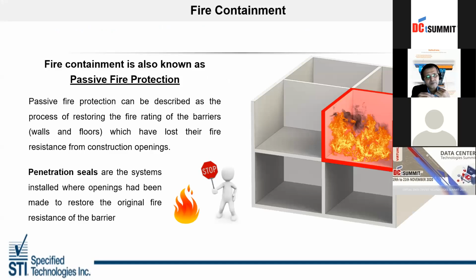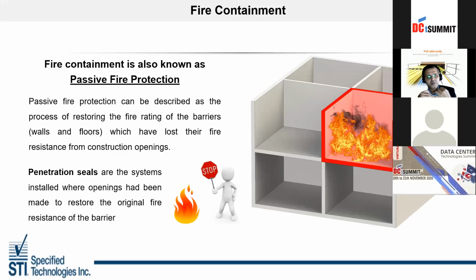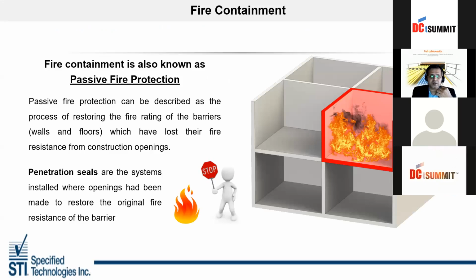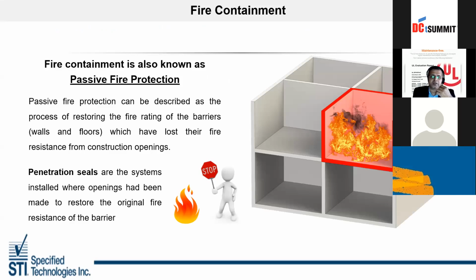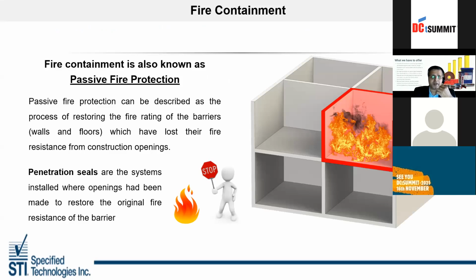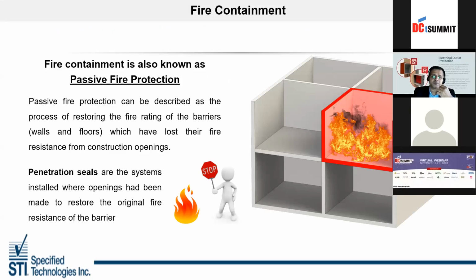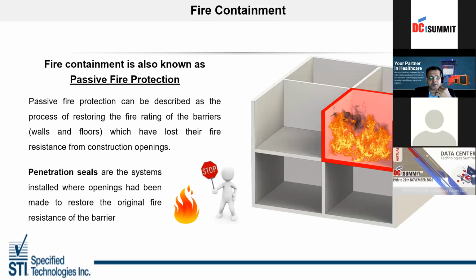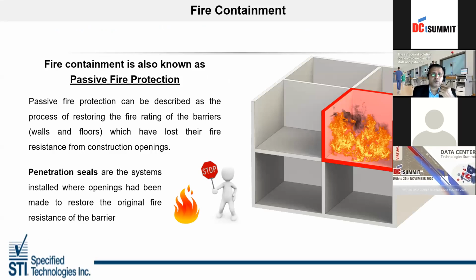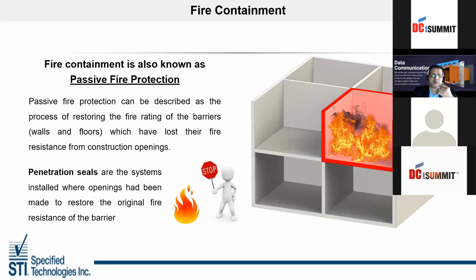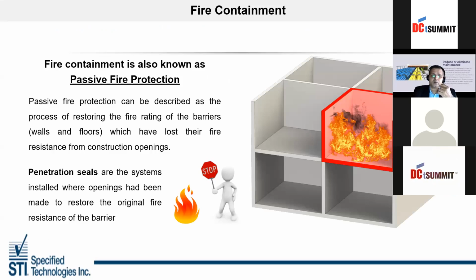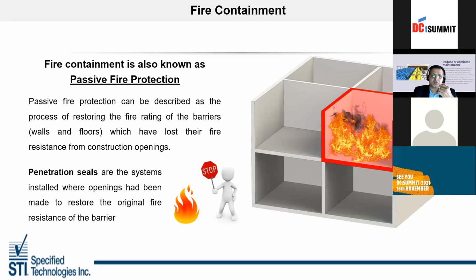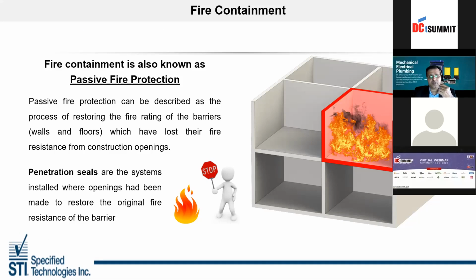What is a passive fire stopping system? If you see, I've just tried to explain with a box, like it's a floor, and the fire happens. The fire is contained there itself. The reason is there are no through penetrations. There's no hole in that particular wall or floor. So the fire is suppressed there itself. A passive fire stopping system is used wherever there is a through penetration in a fire-rated wall or a floor, and those areas have to be sealed with an equivalent product.